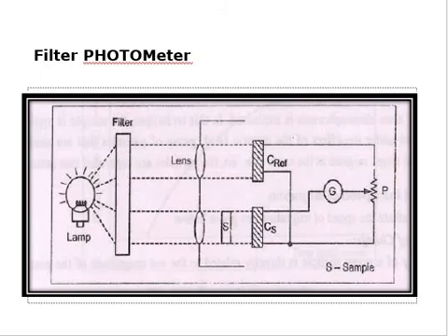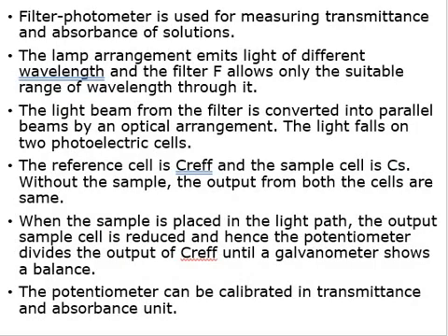After taking all the readings, then we can remove the sample solution and make the circuit again zero. Because if this is not done, then when we place the other sample, that will show some constant value in the system and that will create an error. After every experiment, the system has to be calibrated in order to ensure the reading to the correct value.